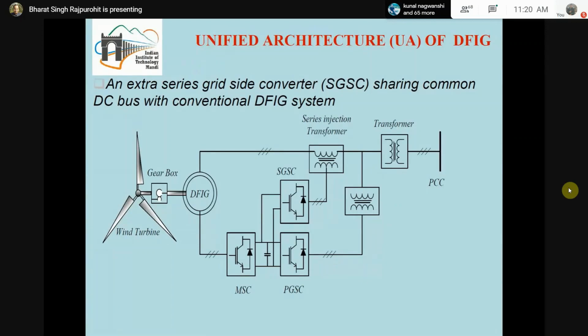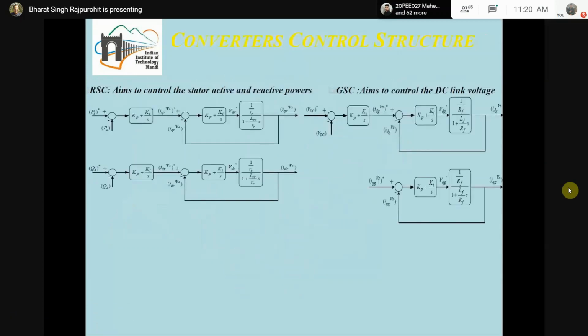papers is that the doubly fed induction generator has huge oscillations during abnormal conditions. We have also done a small signal analysis of that, and we see that there are two poorly damped poles in the stator flux, which play the main role in the huge oscillations in the voltages, flux, and currents, and directly show up as torque oscillation. By providing this series compensation, these stator flux poorly damped poles have higher damping, and these oscillations are reduced. So I have some of the results with me.